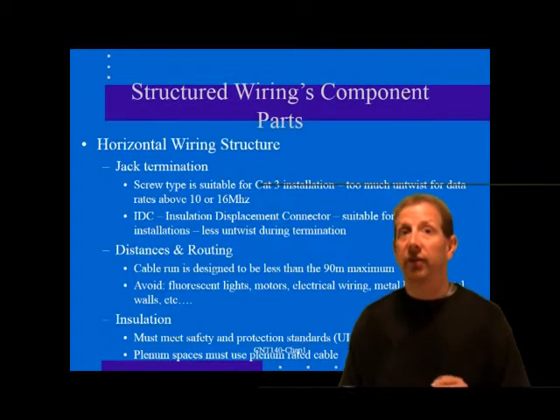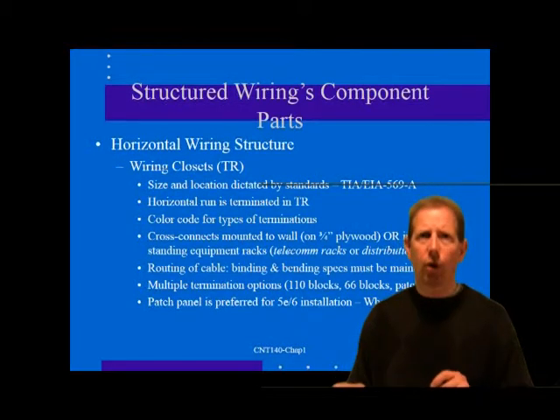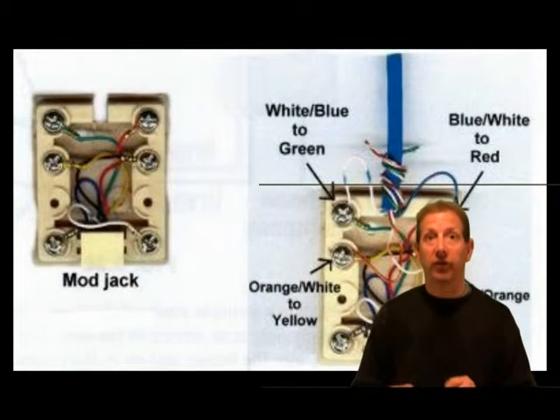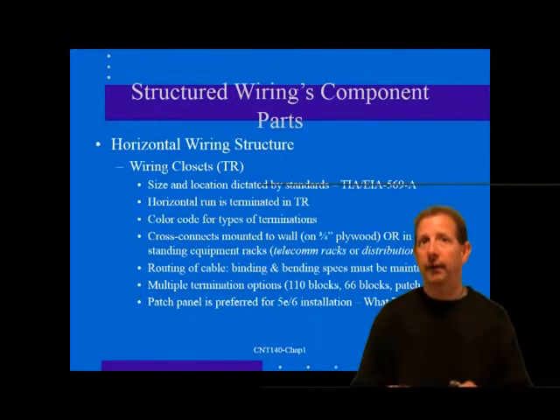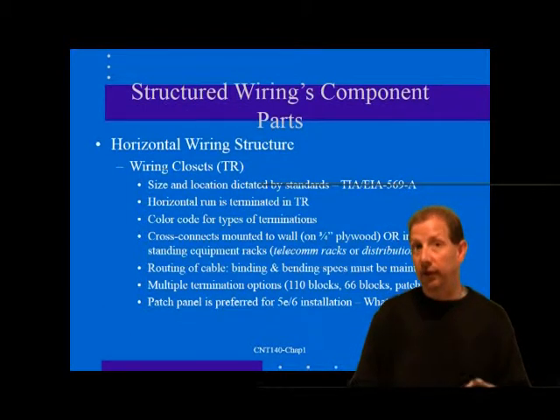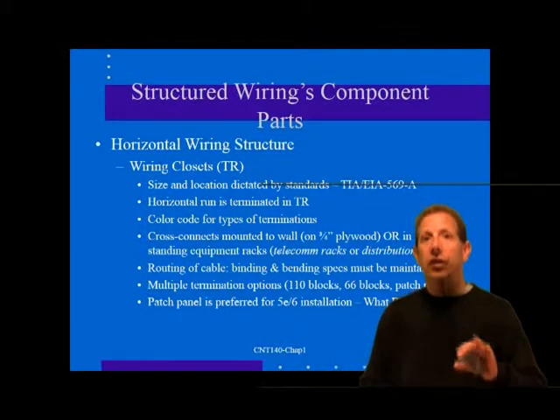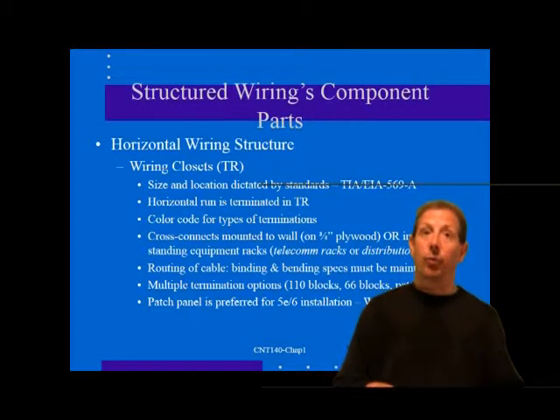Horizontal wiring is specified according to the performance categories defined in 568C. Both cable and connecting hardware must meet performance guidelines appropriate for their use. One factor affecting performance in outlet jacks is the method of wire termination. Screw terminations were acceptable in Category 3 installations but are prohibited in Cat 5e or Cat 6 installations because of performance constraints. Cat 3 is adequate for 10 or 16 MHz bandwidth networks, Cat 4 for 20 MHz, and Cat 5e for 100 MHz.